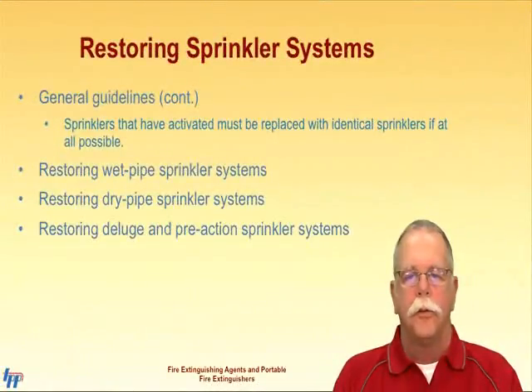Restoring a wet pipe system is really just a matter of replacing the fused head and allowing the alarm valves to reset themselves. Restoring dry pipe systems is more complicated, and the steps for resetting a dry pipe valve can be found in the test section on dry pipe system trip testing. The process for restoring a deluge or pre-action system varies from system to system. Again, the bottom line is that restoring the system, while desirable, should only be done by authorized personnel willing to accept the associated liability, or as authorized by your agency.